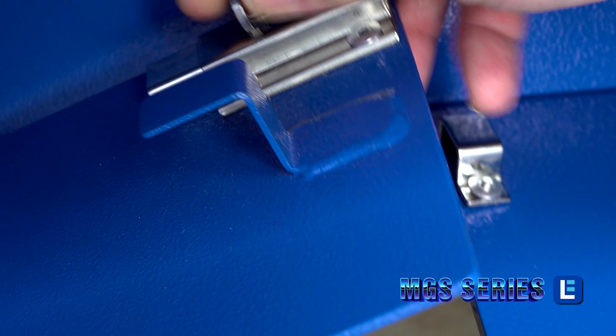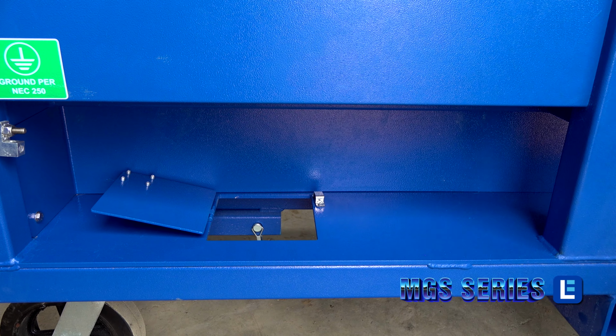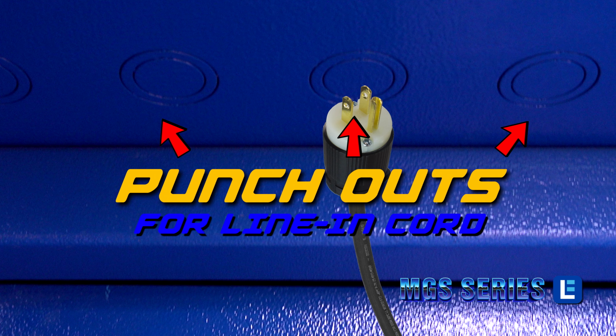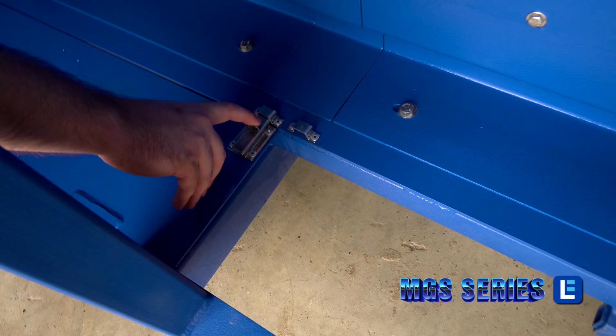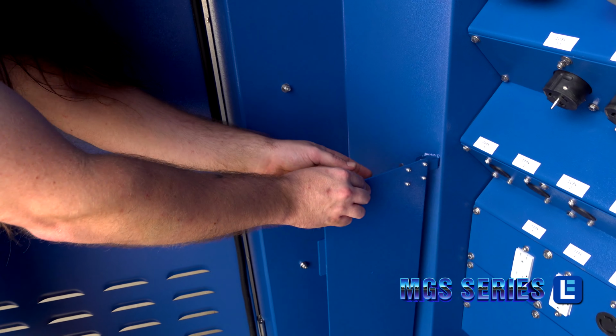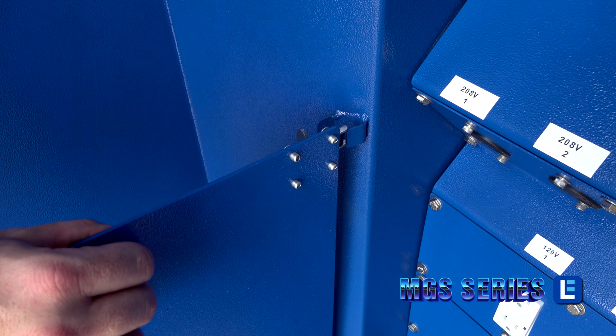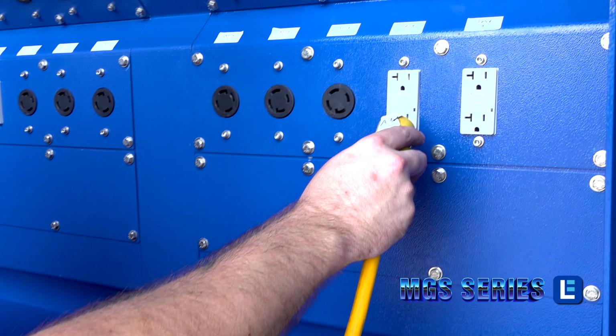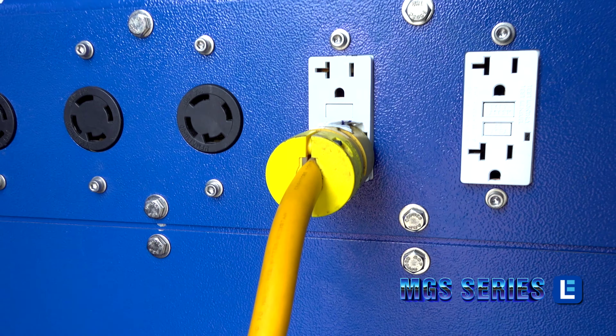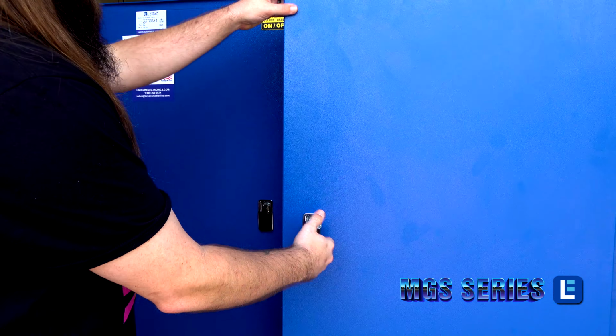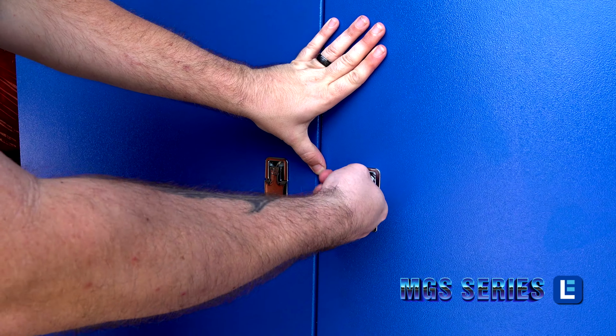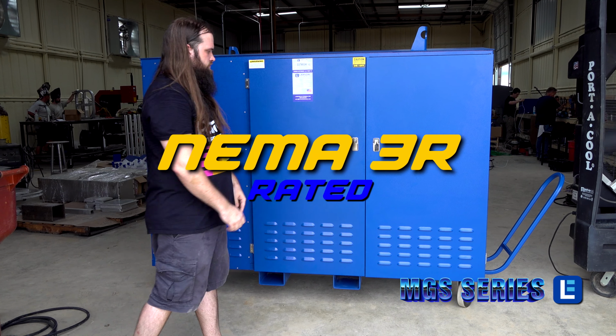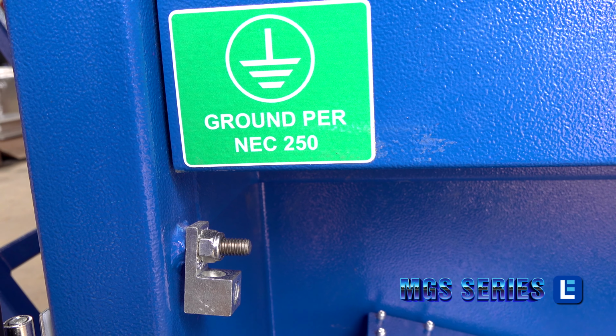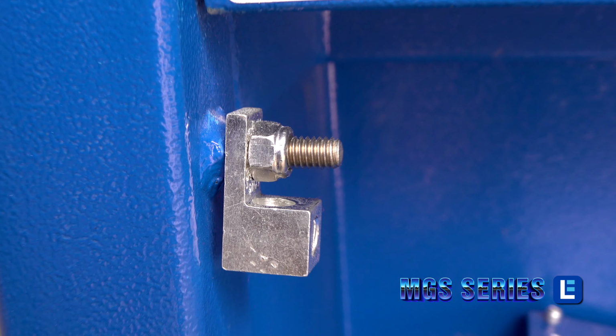A customer-provided line-in cord brings three-phase power to the main circuit breaker on the primary side. Wiring for devices can be run through the trapdoor. This allows the main receptacle access door to remain closed while in use, keeping all receptacles covered and NEMA 3R rated. The transformer is grounded to the frame, and we provide a grounding lug on the frame for the earth ground.